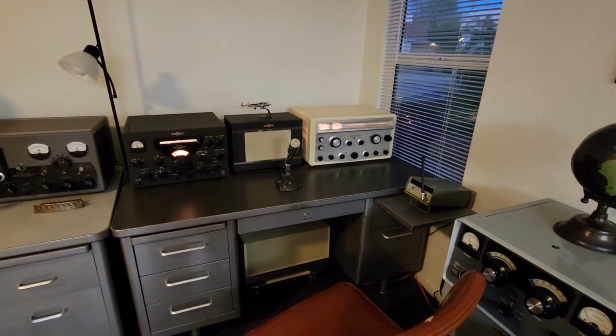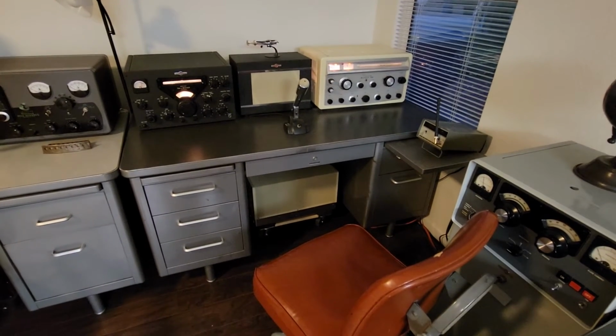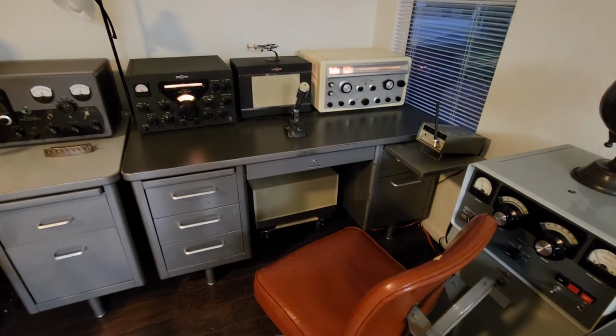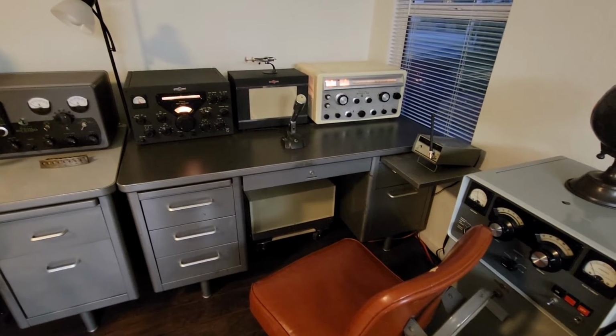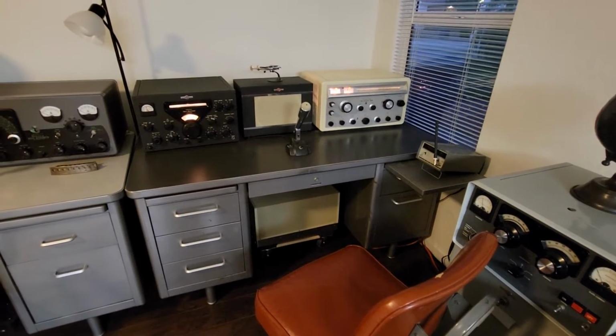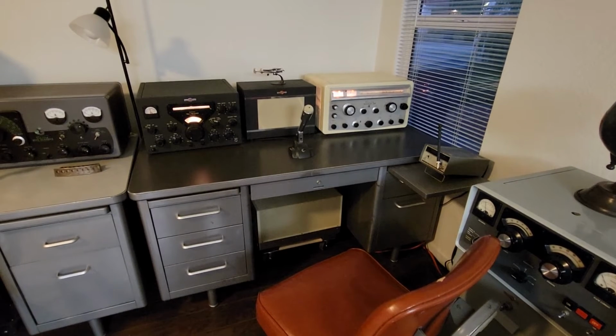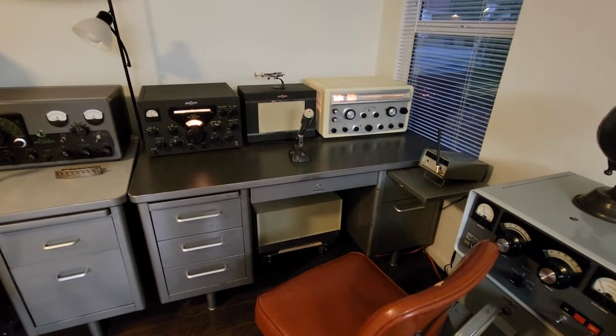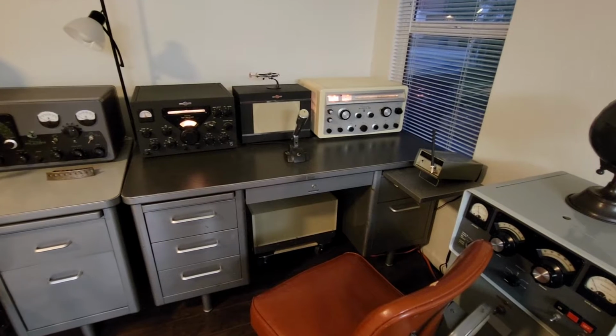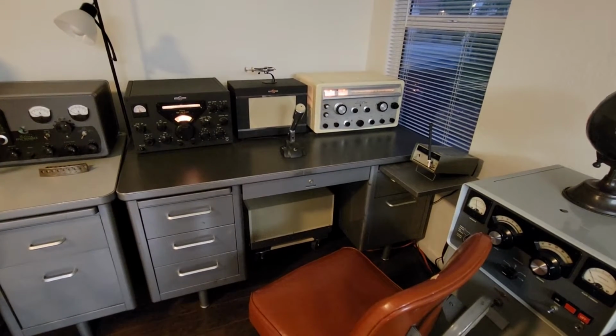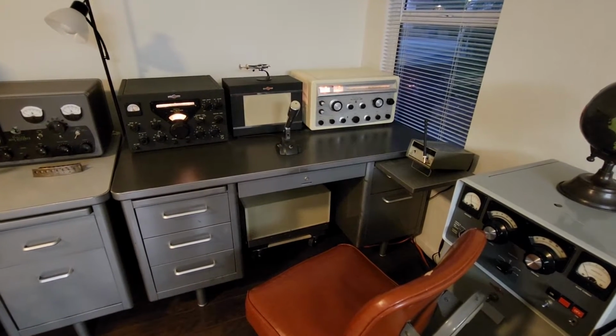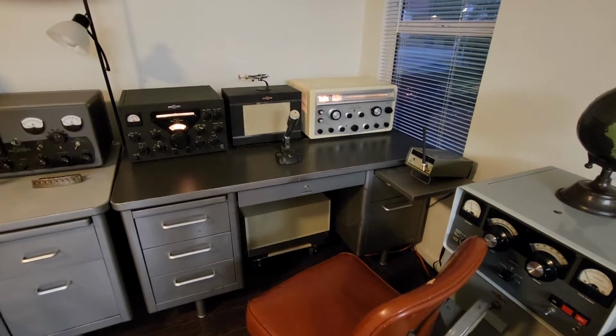and completely restored it. So the power supply's down there on the floor - that has all new caps. The exciter power supply and the high voltage supply has been rebuilt. Screen voltage has been put on the high tap. There's a new relay in there, new cabling.